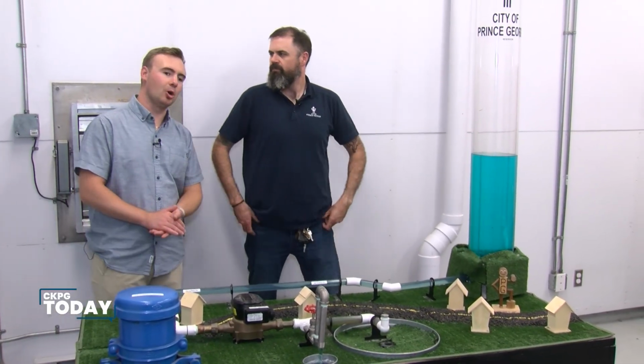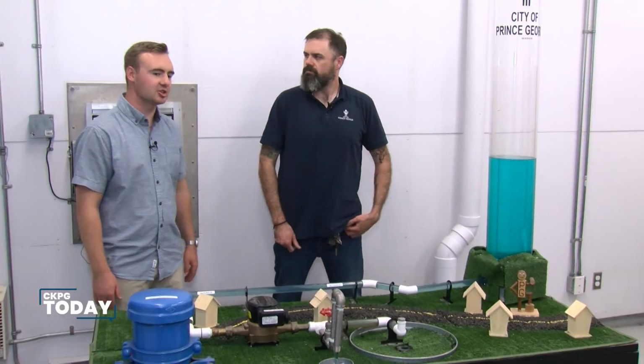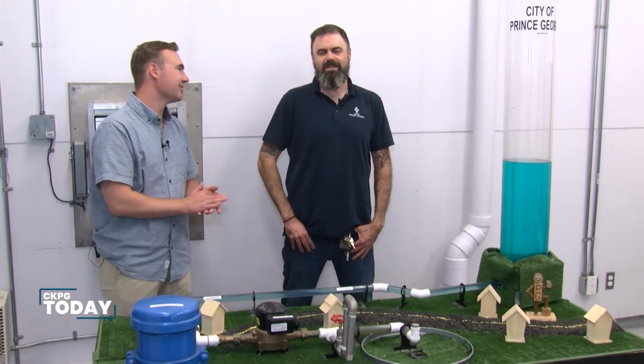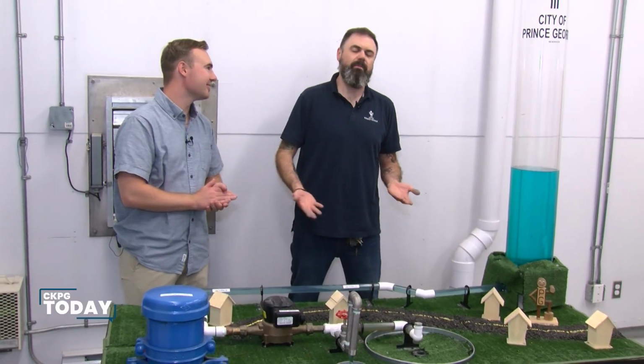So when people go, all those reservoirs, those big concrete things, whatever, those are useless. No. Yeah, so they're actually as big as they are, obviously for water demand, but our biggest thing is fire protection. They are way, way oversized for the water demand of all the residents, but they're built based on fire protection for particular areas.